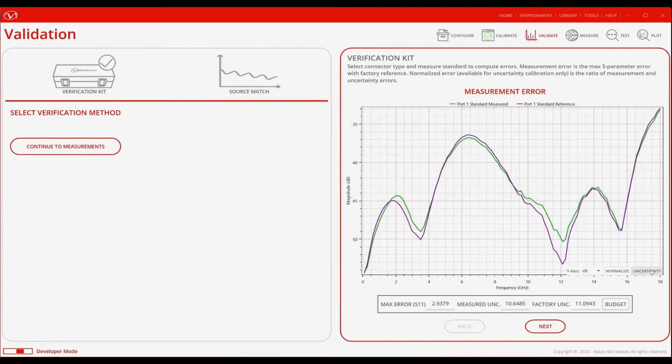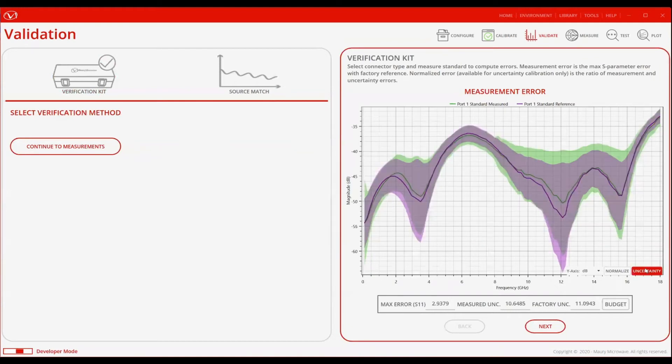But how do you know what is close enough? Isn't this still a little ambiguous and subjective? Well, that's where measurement uncertainty comes in. Let's take a look at the factory characterized measurement data with uncertainty, and the just measured data with uncertainty, and compare the normalized error.